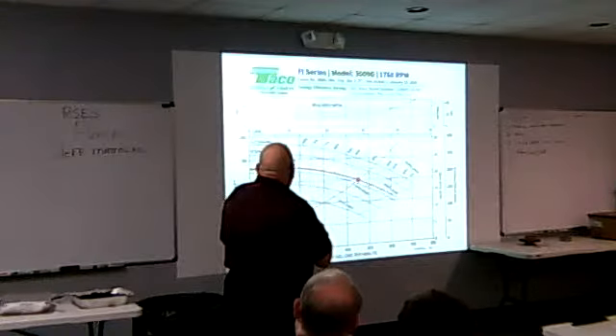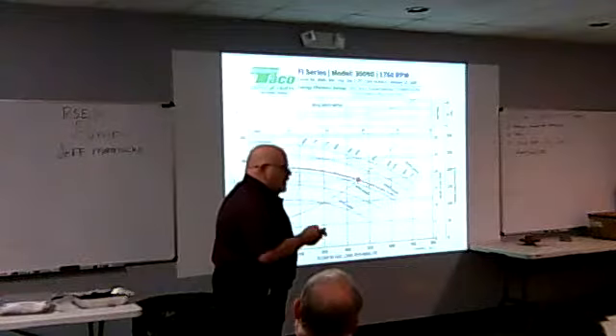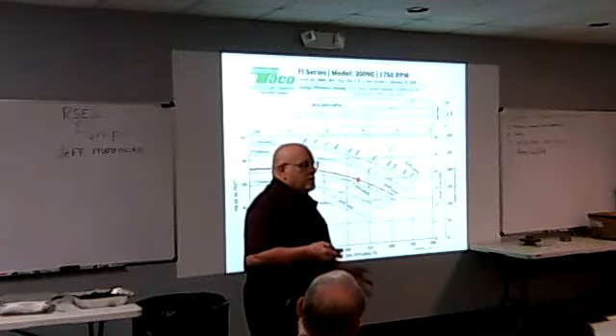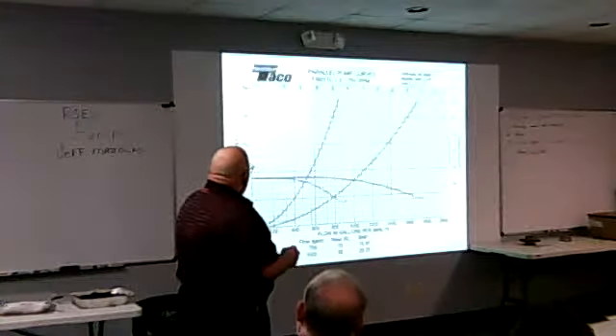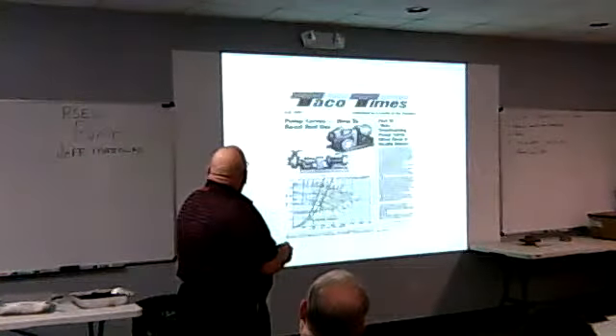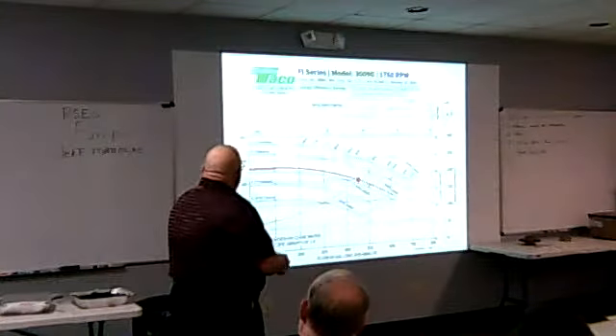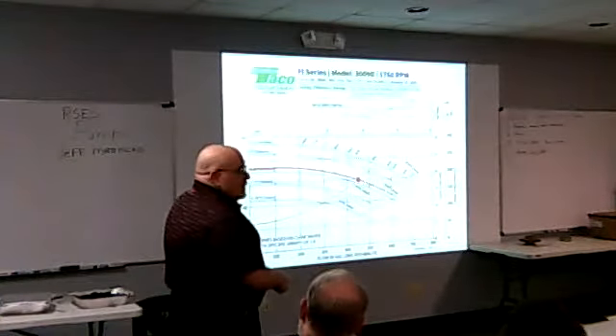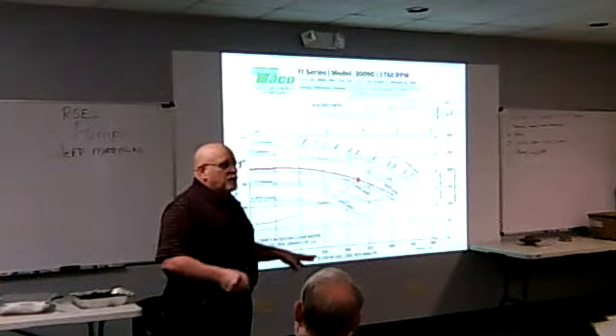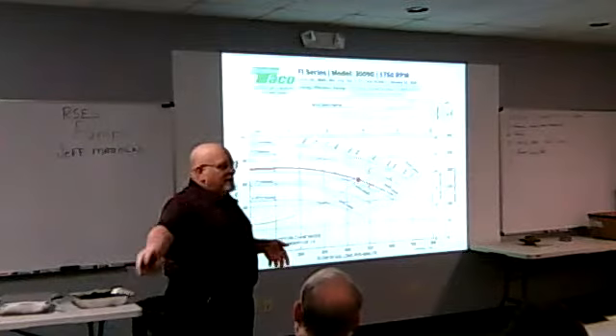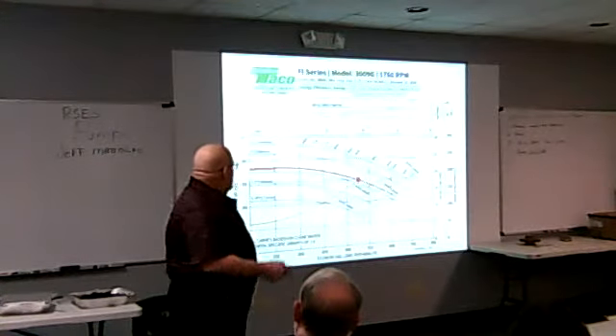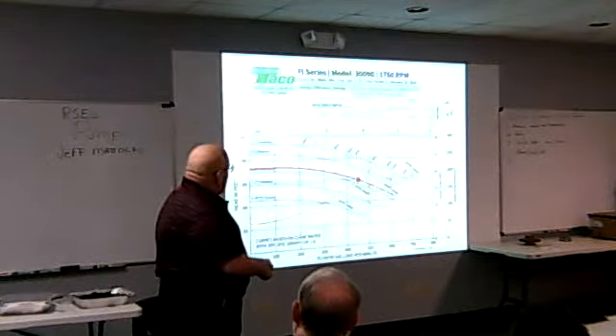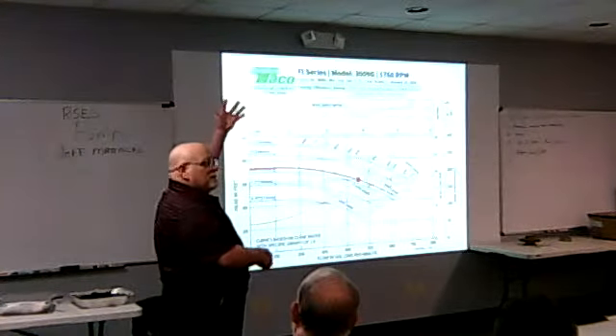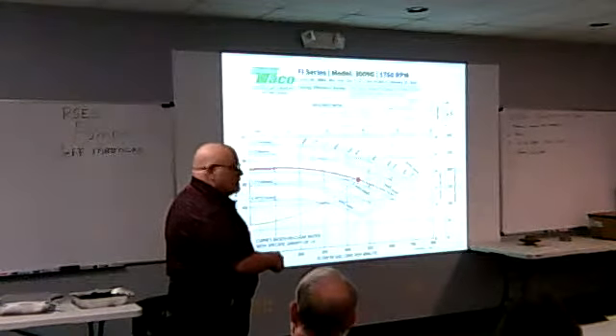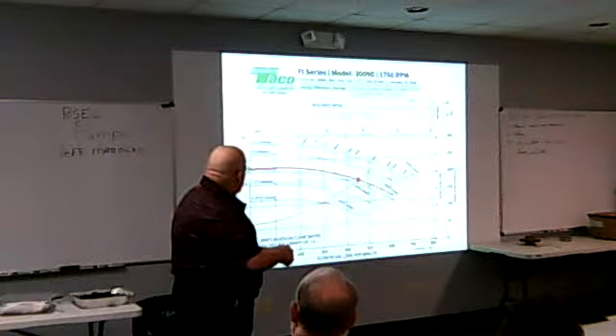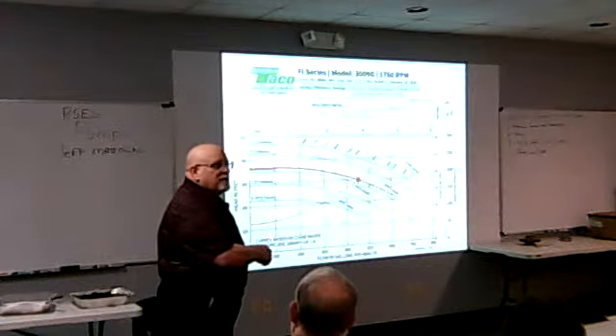Why did I put that one in there? Oh, when you do an open system, like a hydronic booster system, notice all the other, whoops, sorry. Pushing the wrong button. Normally we start at 0 for a hydronic system because it's a closed loop system. I have no static head. It's all equal. I got 100 pounds on this side, I got 100 pounds on that side. It's equal. In the domestic system, I might start at 26 pounds or 24 pounds, and I'm boosting it up to building 100 pounds. Well, I have to take that into account and move this up the curve. I have to add that into my system curve because I'm not starting at 0. I'm starting here at static.